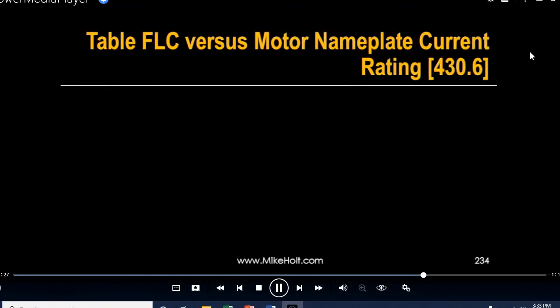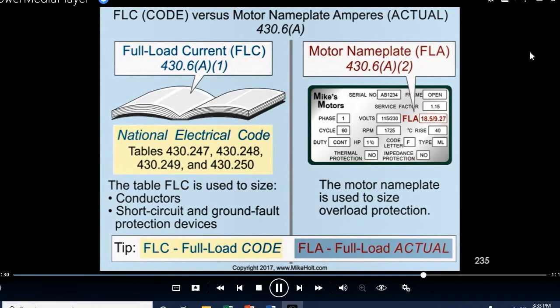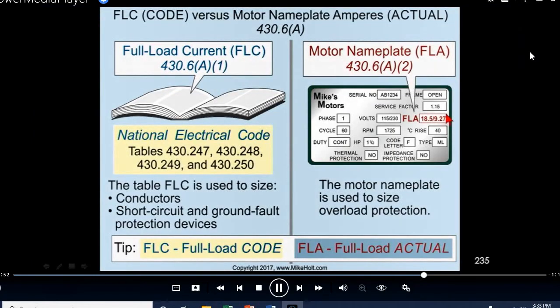Motor nameplate versus FLC. This is not a motor class here. We have an entire video that deals with all kinds of motor conductor sizing and calculations, and we'll be covering that at another time. Actually, that'll be next month. So I'm quickly going over motor calculations. You really need the calculations video to understand all the calculations in motors. So let's go through it really fast. Ready for this? Motors have a nameplate, and they have a nameplate rating. And then you have the National Electrical Code that lists the different currents of a motor.